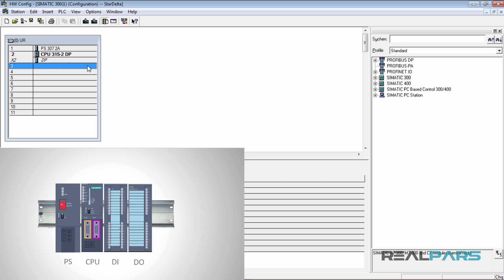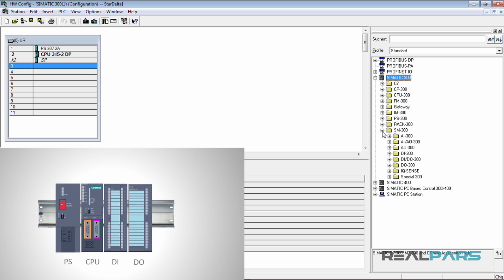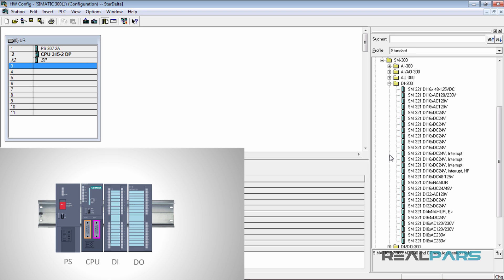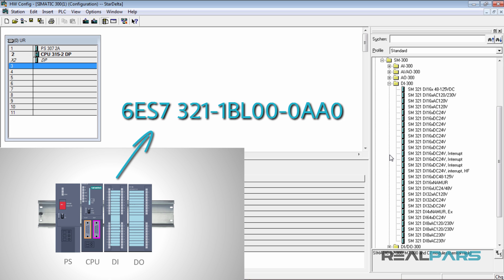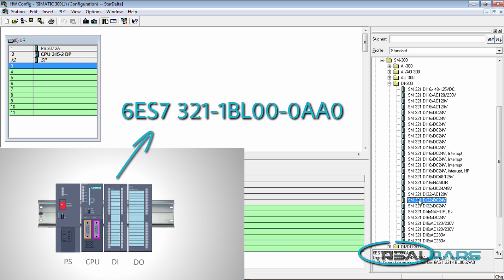The next module that I need to add to the rack is a 32 point digital input module. To find this DI module, I should look into the SM300 folder and then open the DI300. As you can see, there is a long list of different digital input modules. The order number of the DI module that I have on the rack in the actual environment is 6ES7-321-1BL00-0AA0. So here in the software, I need to double click on this module and add it to the rack.